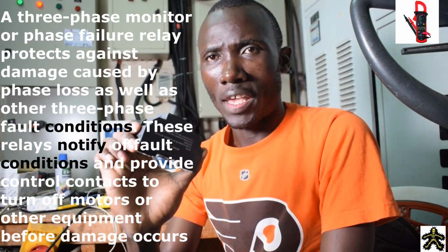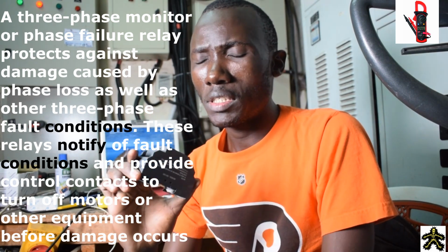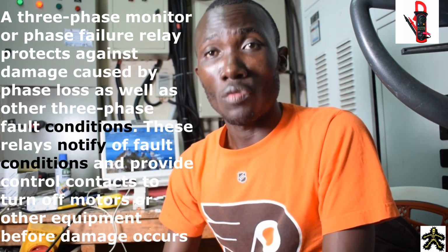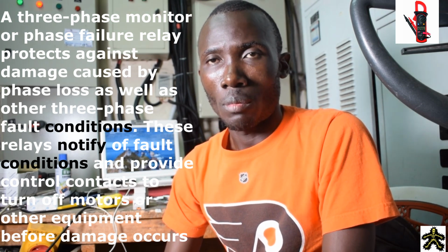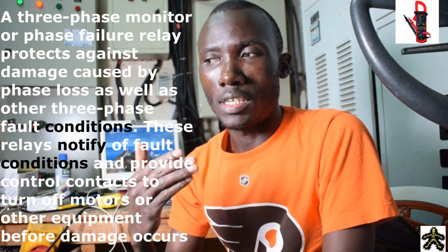So this phase failure device, one, helps us to avoid single phasing, because single phasing is very common in three-phase electrical circuits. Perhaps a fuse at the supply transformer can blow, and your circuit is on, your motor is running, your three-phase pump is running. What happens is one phase will be missing, and if you don't have this, definitely that motor will blow. Single phasing is really bad for drives.